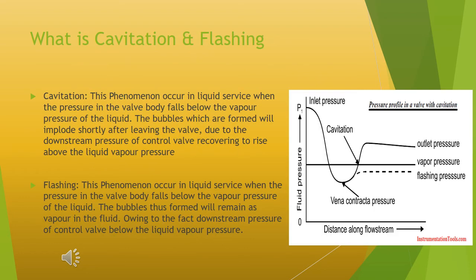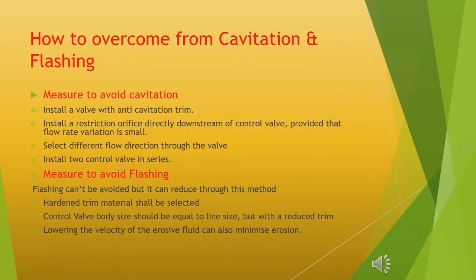What is cavitation and flashing? Cavitation: this phenomenon occurs in liquid service when the pressure in the valve body falls below the vapor pressure of the liquid. The bubbles which are formed will implode shortly after leaving the valve, due to the downstream pressure of the control valve recovering to rise above the liquid vapor pressure. Flashing: this phenomenon occurs in liquid service when the pressure in the valve body falls below the vapor pressure of the liquid, but the bubbles remain as vapor in the fluid because the downstream pressure of the control valve remains below the liquid vapor pressure.